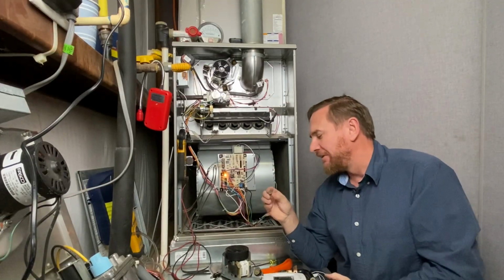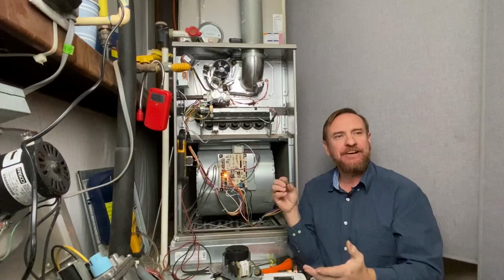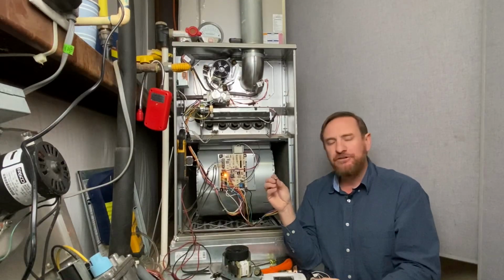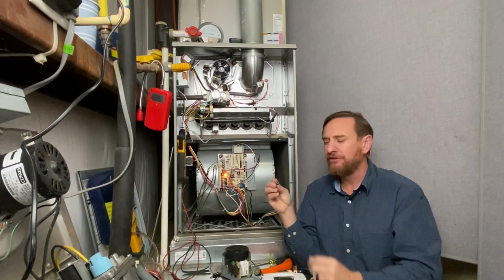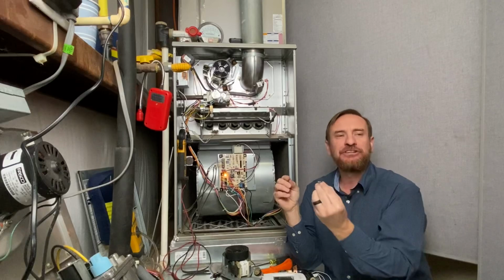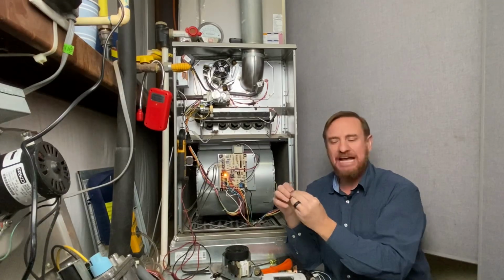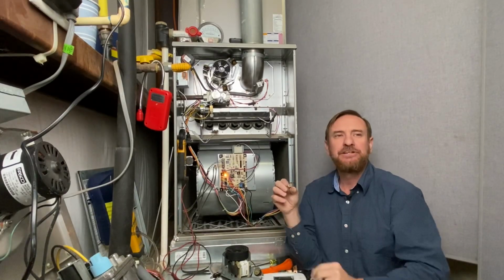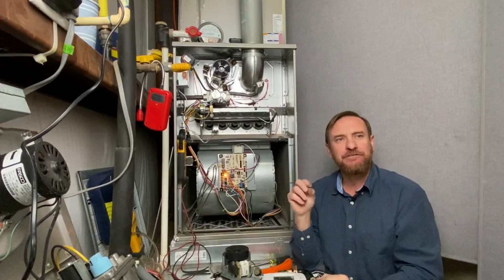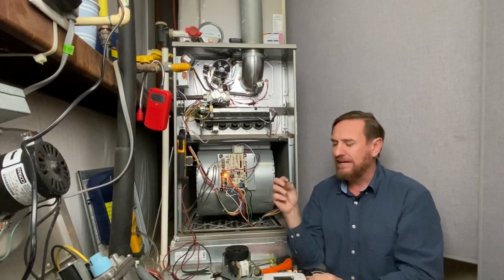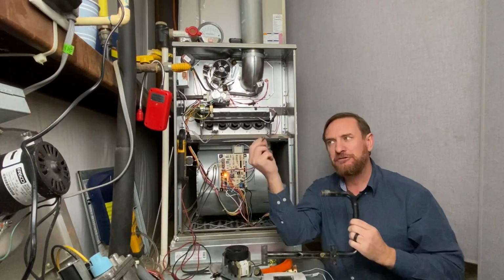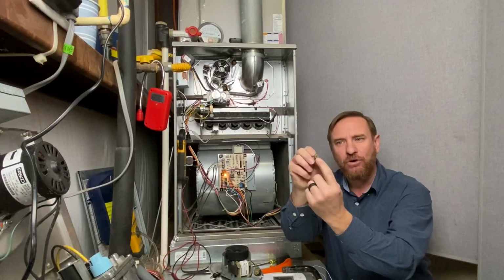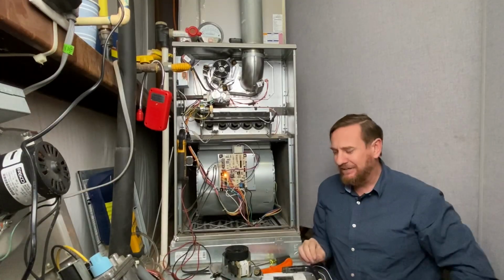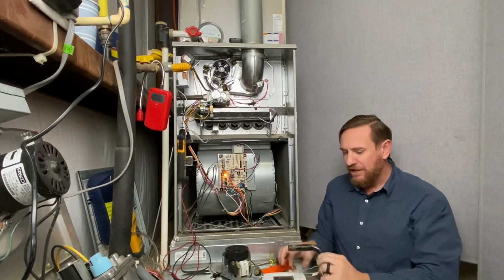Now the size of that number depends on the manufacturer and the altitude. Different altitudes sometimes require different numbers for gas regulation, and there's certainly a different number between propane and natural gas. We'll get into that later, but a lot of units have been ruined because they weren't converted from natural gas to propane correctly. So gas flows through the manifold, to the spud, through the orifice, the hole in the very, very center. Then as it gets interesting is it goes into the burners.